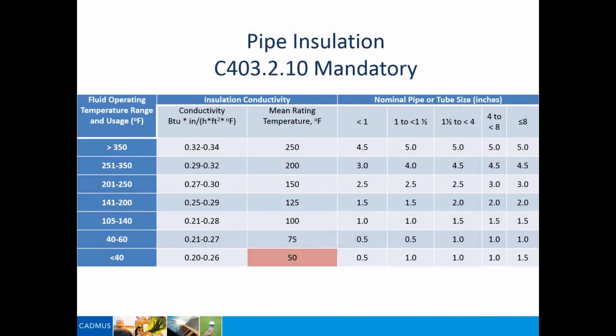So the other thing is, we are going to seal and insulate our ductwork, and our refrigerant piping for your mechanical systems also has to be insulated. This particular table is set up based on fluid temperature. In the left-hand column, you have your fluid operating temperature range, then a conductivity value for the insulation itself, and then the thickness of the insulation in the far right columns.